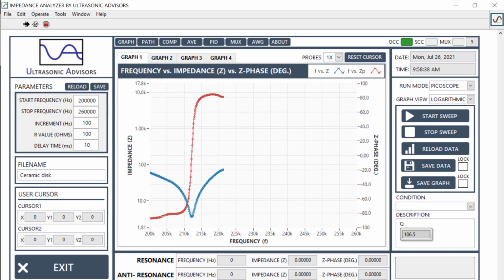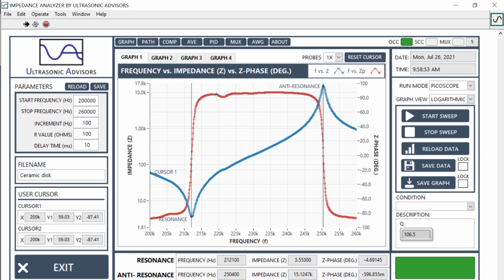So this phase bend, these are actually spurious resonances which occur due to the holding of the transducer, and potentially also due to material non-uniformities. You'd like to think your material is exactly the same all around, but that's not true. Due to the manufacturing process, the process of poling, there are electrodes applied. Sometimes the lack of electrode is used to designate a positive or a negative symbol, just showing how the poling process occurred. So this is our baseline, let's say. So we're at 212 kilohertz and 3.55 ohms.